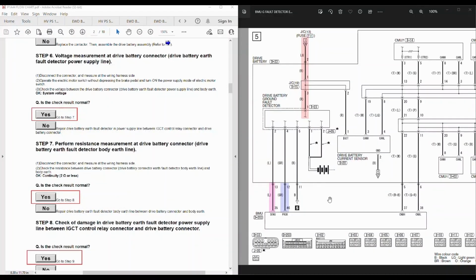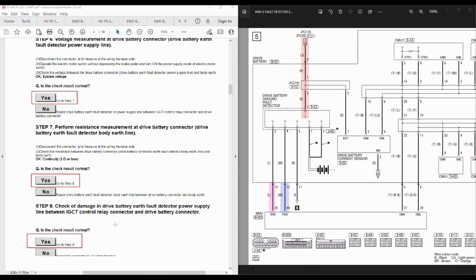That would have been disconnecting this connector here and measuring from this point, point 11, to chassis ground to confirm that we've got a good ground there. And I think minus 74 milliohm is certainly good ground. That was test 7, so now we go to test 8.